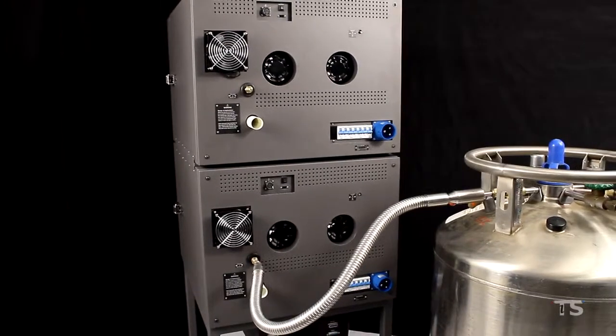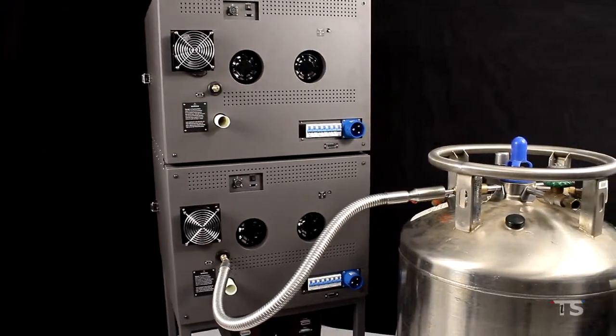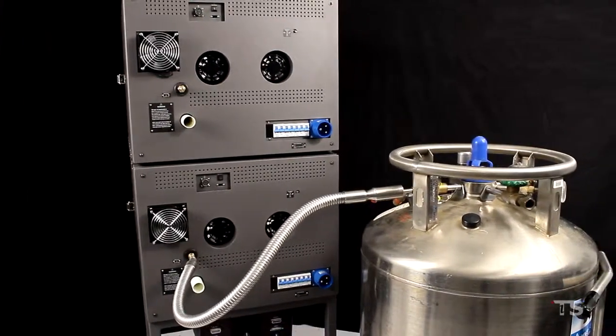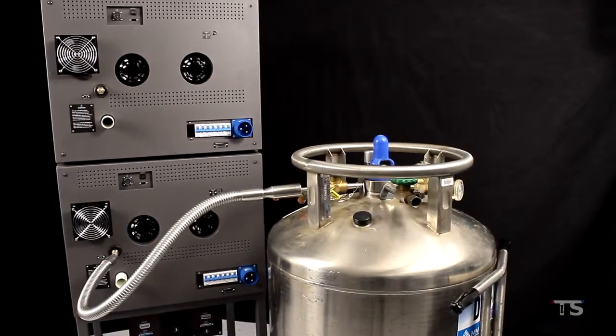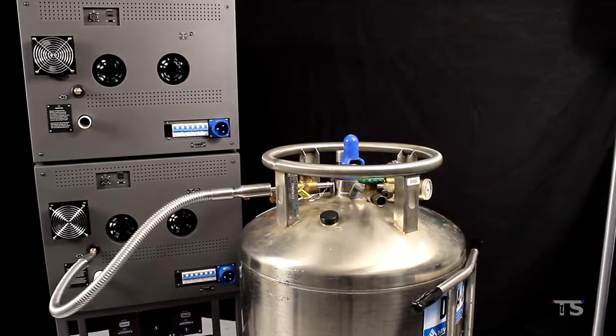This process ensures that the delivery line is free of air. This is important because air in the line carries moisture and moisture can freeze and create a blockage in flow of coolant, thereby reducing your thermal chamber's performance.